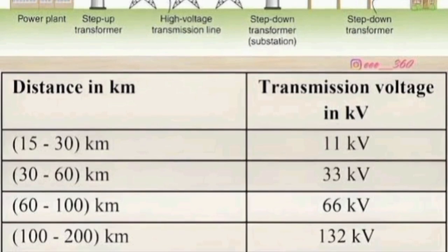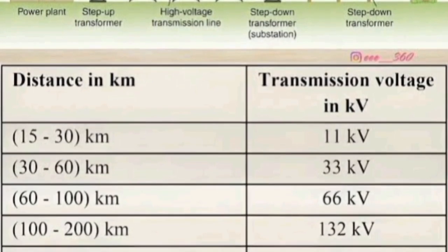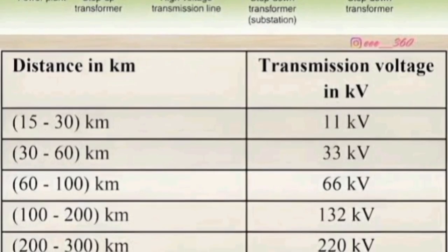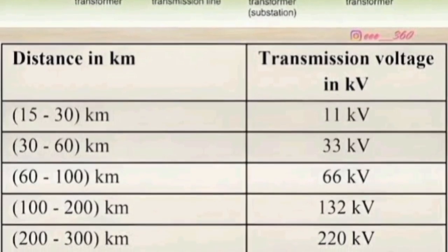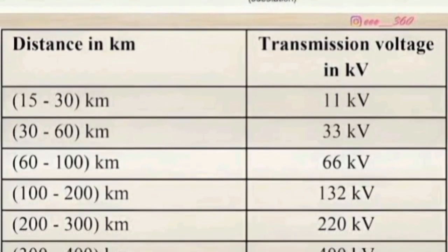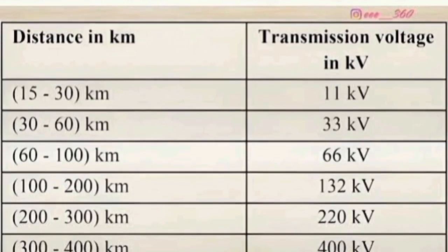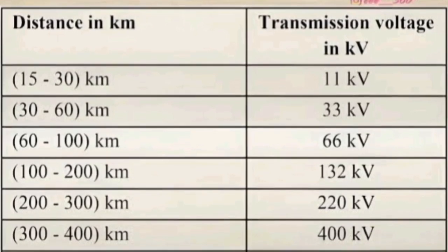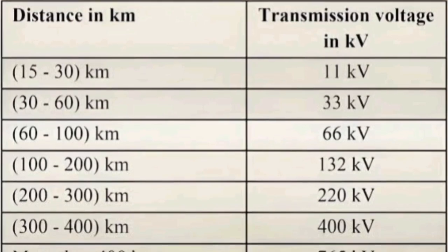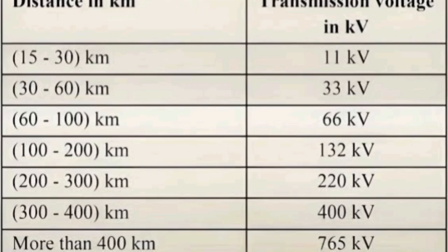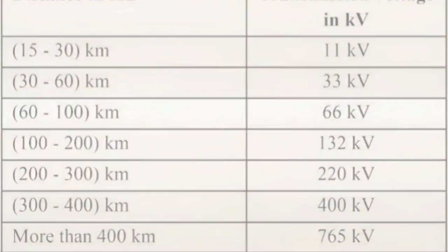Lower current reduces line losses and allows smaller conductors relative to delivered capacity. Transmission voltages may range from 69 kV to 500 kV, depending on region and infrastructure. Before reaching the facility, power is stepped down at regional substations and delivered to the data center campus at medium voltage.